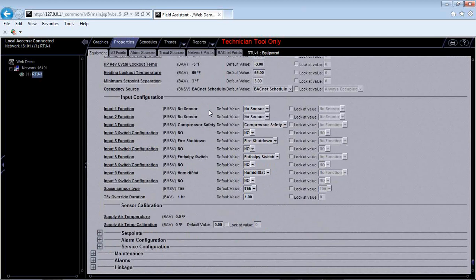Now I want to configure the inputs for my rooftop unit controller. Like I mentioned before, to run this rooftop controller standard bare bones, you need a supply temperature sensor and a space temperature sensor, and then your transformer. Other than that, you technically don't need anything to run it. It will run by itself. But there are other options you can use based on what type of unit you have. So if you have a humidifier or are doing dehumidification with the rooftop, you would require a humidity sensor to maintain that set point.